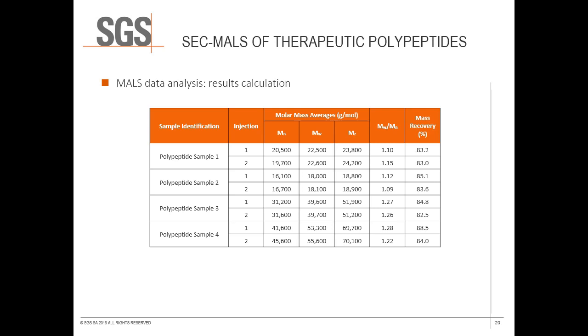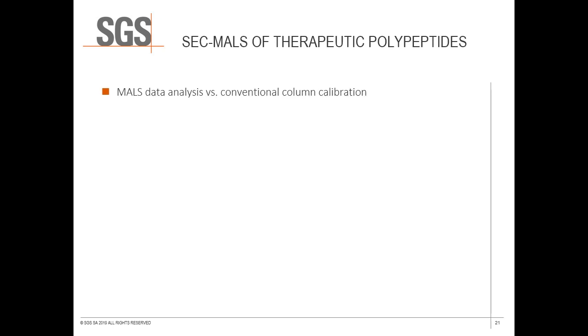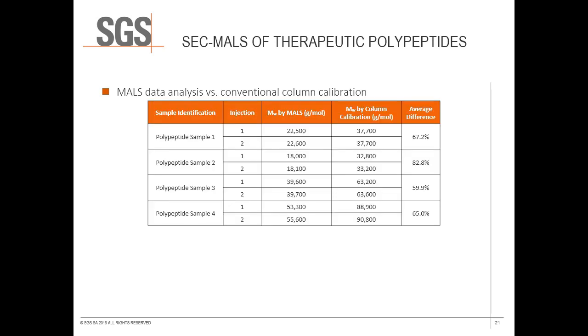This is notable due to the effect this will have on the accuracy of calculated number and z-average molar masses. The Mw, or weight average molar mass, is directly measured by light scattering analysis and is independent of the effectiveness of the chromatographic separation. The number average and z-average molar mass values are calculated based on molar mass and concentration values for each slice across the chromatographic peak. Therefore, the accuracy of Mn and Mz are strongly dependent on the separation. For this particular set of samples, results were also calculated using conventional column calibration.